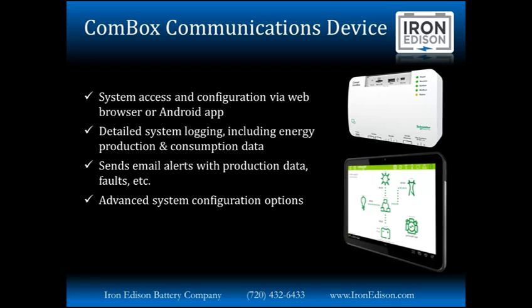The bottom right shows the Android application, which is also the same main display you would see if logging in with your computer, that gives you a map of all the different components and allows you to track in real time solar production, grid usage or energy sold back to the grid, load consumption, as well as battery voltage and generator usage. The ComBox allows us to log up to 20 data points on a second-by-second basis and can send email alerts with production data, faults, monitoring, etc. It also unlocks some advanced configuration options that aren't available directly through the system control panel.